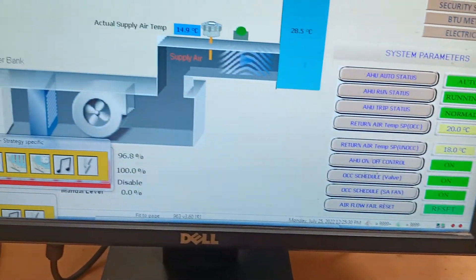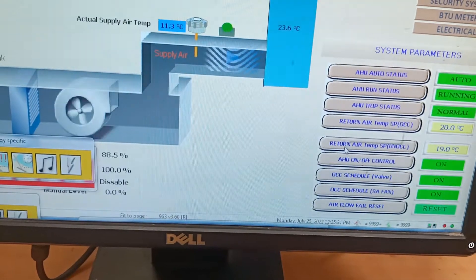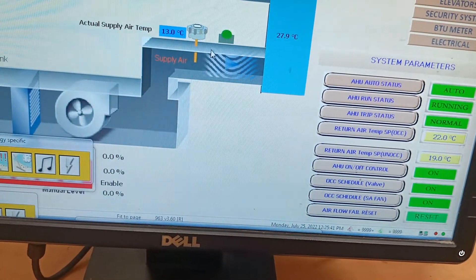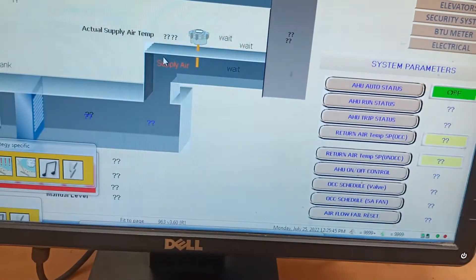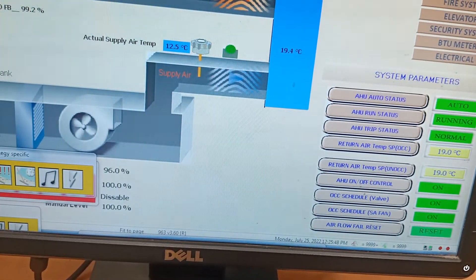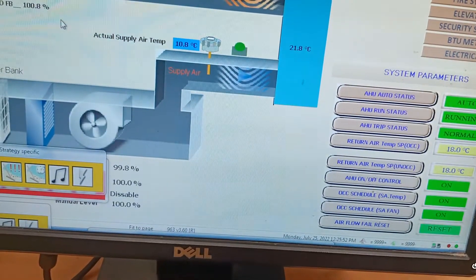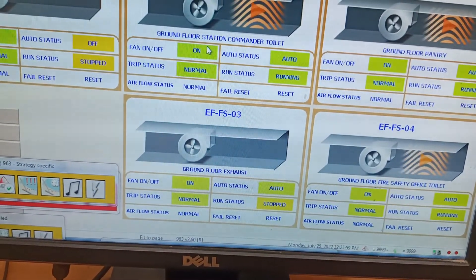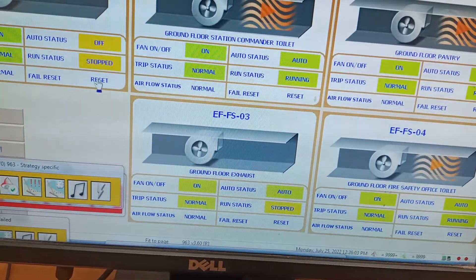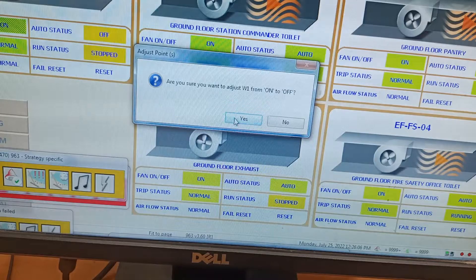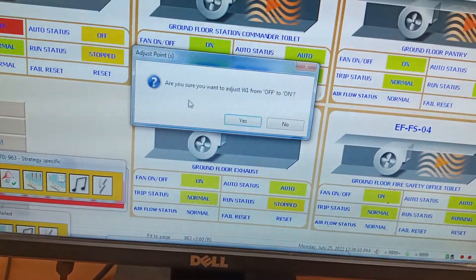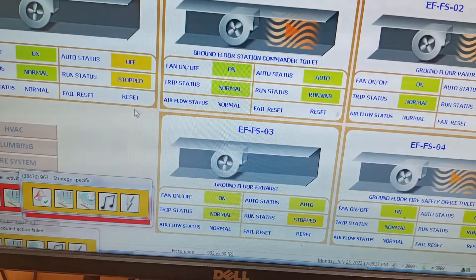Now we are checking whether all FCUs and all AHUs are running or not. Here it is in running position. At position six we will check — it is also in running position. Exhaust fans are all running, but two exhaust fans are stopped. I will try to turn on and reset them. Actually, they are not starting — there is some problem with the existing system. The other fans are running fine.